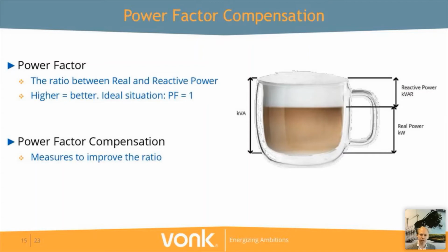Power factor is one of the items that you need to comply with when it comes to grid regulations. In many cases, the power supply by itself, in this case the rectifier, is not performing sufficiently to be compliant by itself. Therefore, it's a common measure to add power factor compensation. These are measures to improve this ratio and be compliant with the requirements.